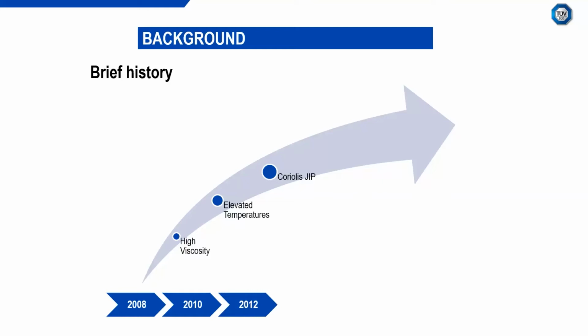And one of the main outputs from that project, which finished in 2014, was that there was a requirement for a new facility, a facility that could calibrate Coriolis flow meters close to service conditions, be it temperature and pressure. We already had the high viscosity facility. So we built this new facility from 2014 to 2016.